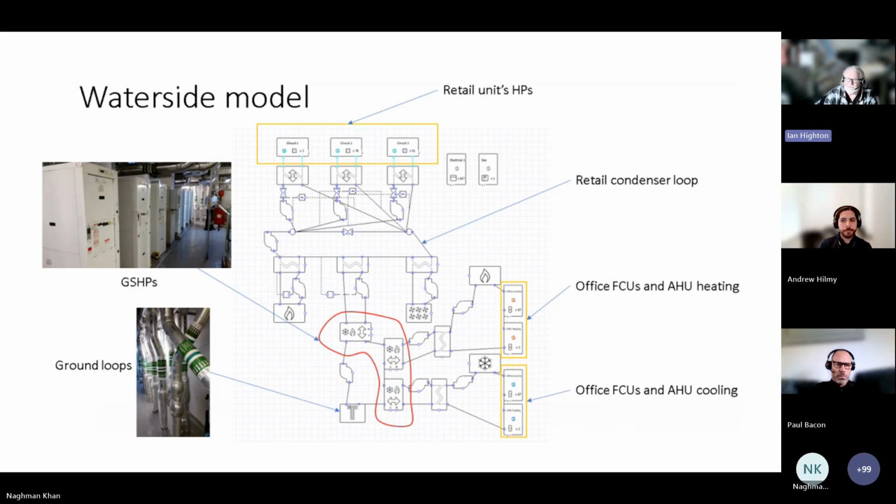And I think the reason they were particularly interested in what we could do is because they had no idea how much money that was going to save over a full year. Whereas we could run the simulation with the really bad humidity control, we could run it with the better humidity control, and then we could tell them from the energy centre exactly how much cost that was going to save, which turned out to be, I think, £50,000 per annum. So that was the thing they were having trouble quantifying, which the software could obviously model and then reproduce, which is good.